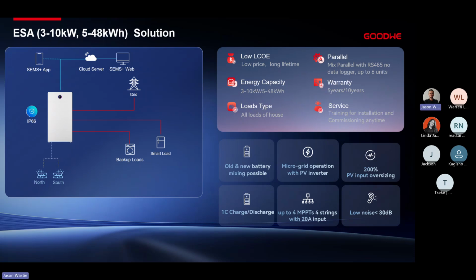Next is our ESA, 3 to 10 kilowatts, 5 to 48 kilowatt hour solution. This is our all-in-one solution: an all-in-one battery cabinet, battery rack with the inverter on top. This is also very new to market for GoodWe, and we have a few different ways we can connect this system. We can mix and parallel up to 6 units, meaning we can have a 3 kilowatt inverter, the 10 kilowatt inverter with a 5 kilowatt inverter in between, and up to 6 of them we can parallel together.